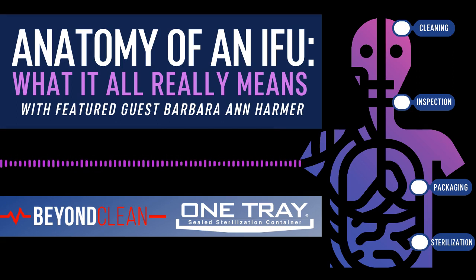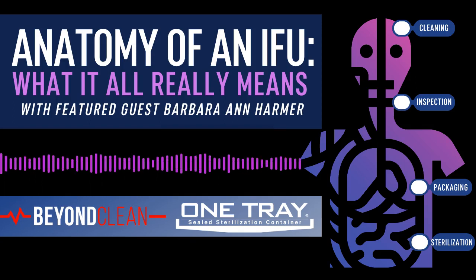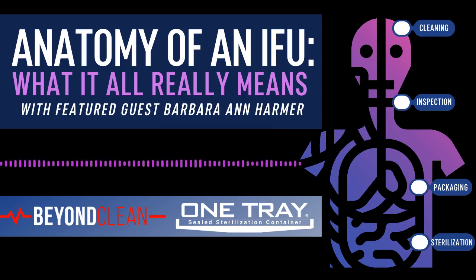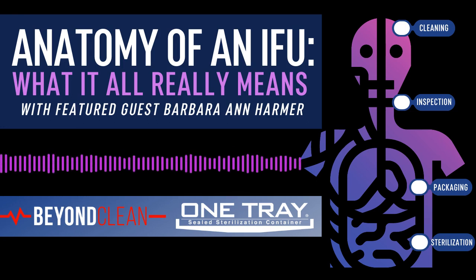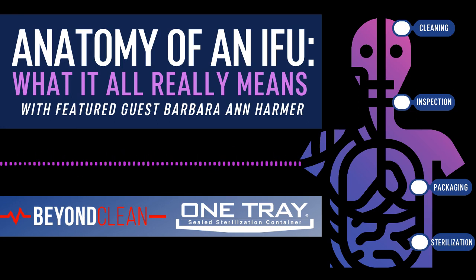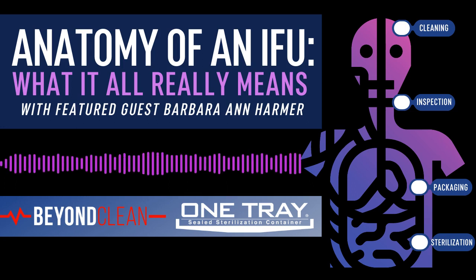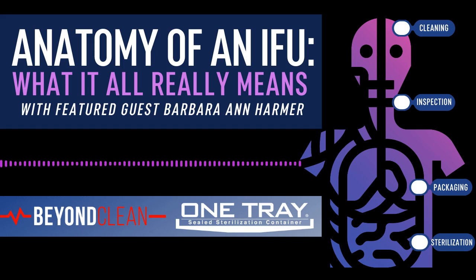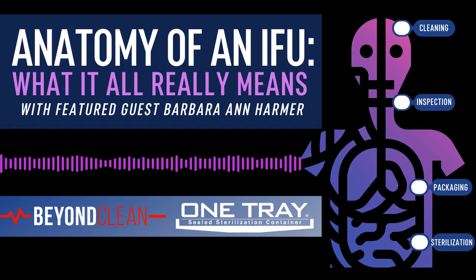The moisture does not compromise the sterility of the contents. These are statements that are in our IFU that has been reviewed by the FDA. Per AAMI recommended practices and guidelines, IST, the owner and the maker of ONETRAY, recommends the facility to develop a policy and procedure regarding the sterility and use of the contents of the container systems that appear to have retained moisture. That can be found in AAMI ST 79.